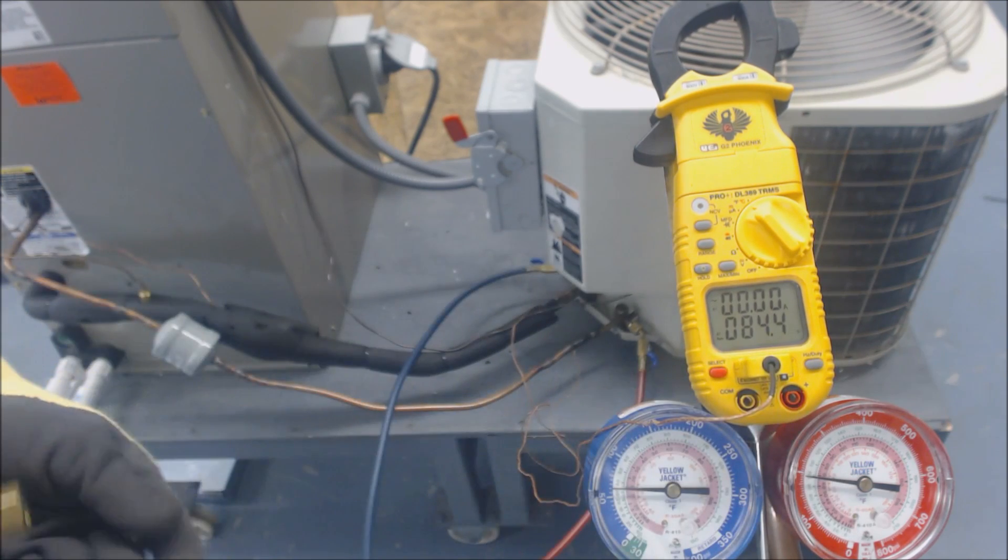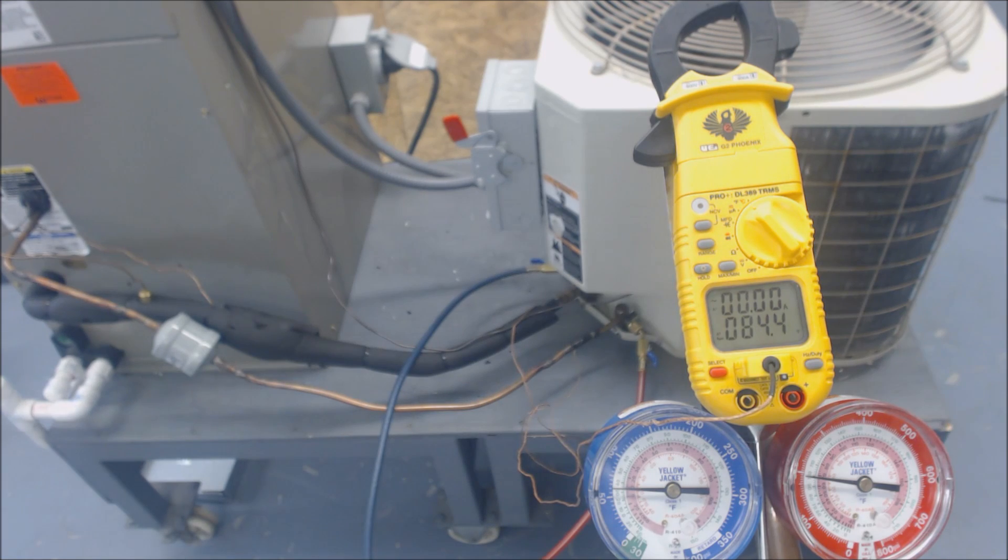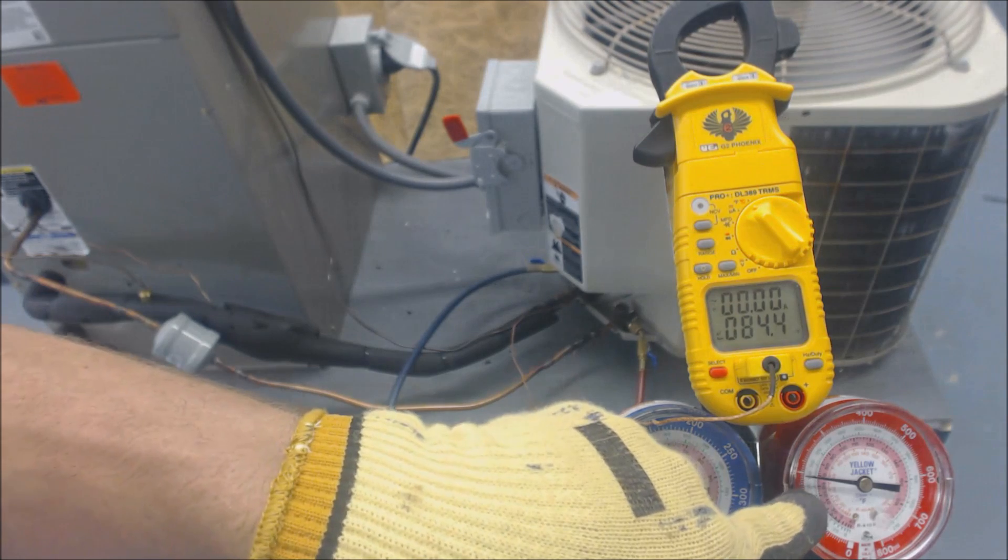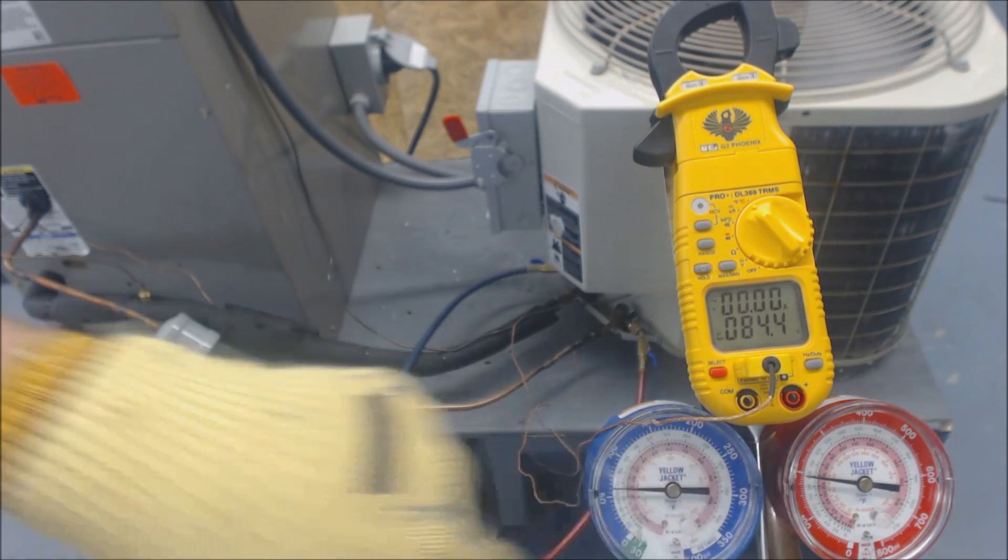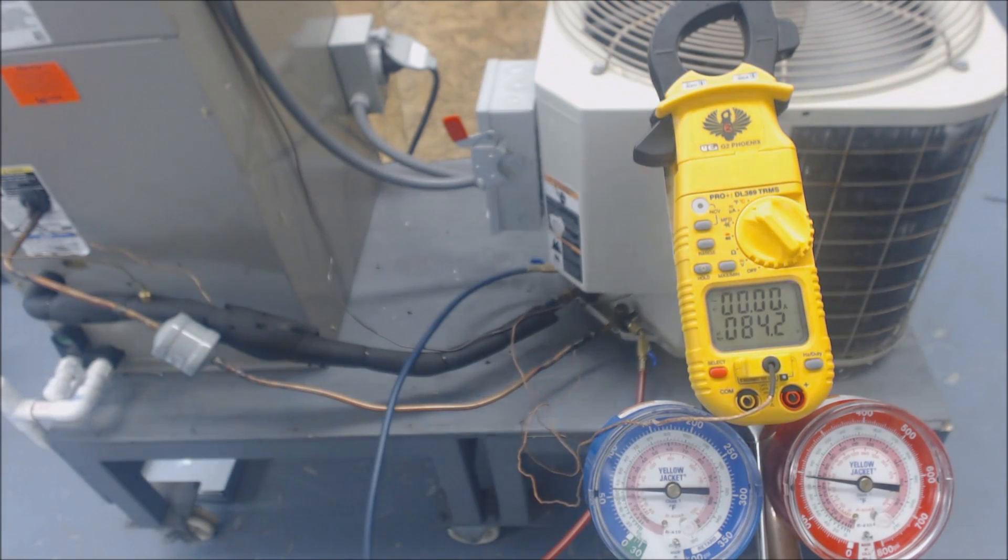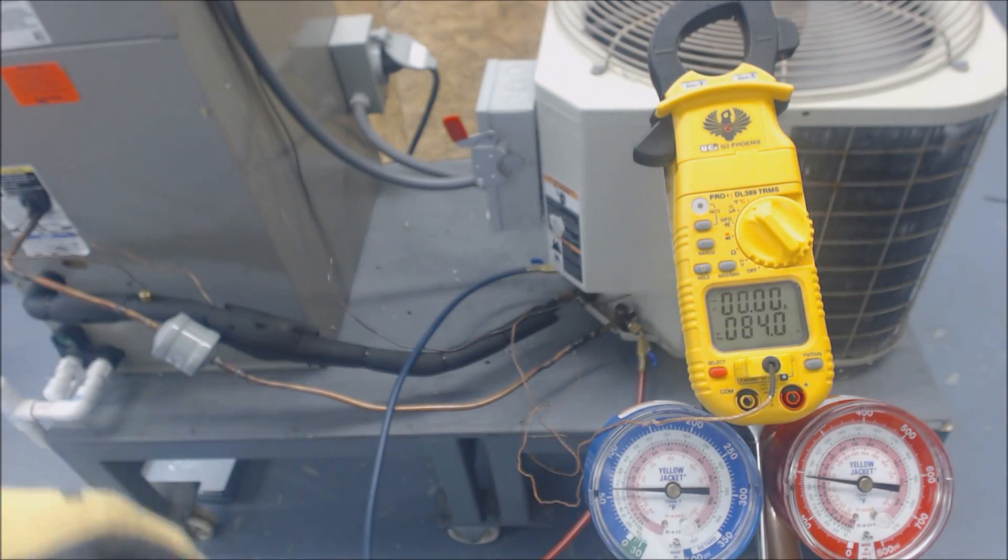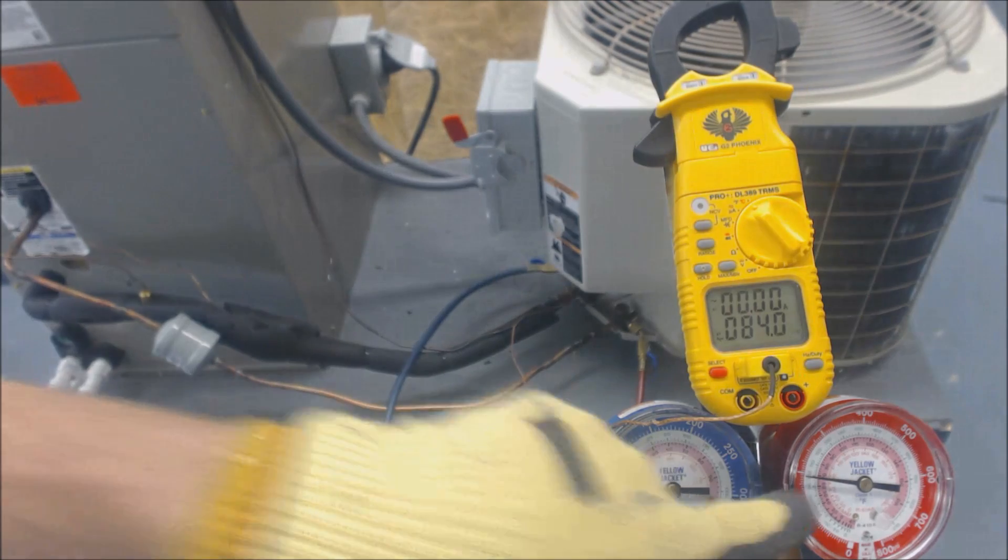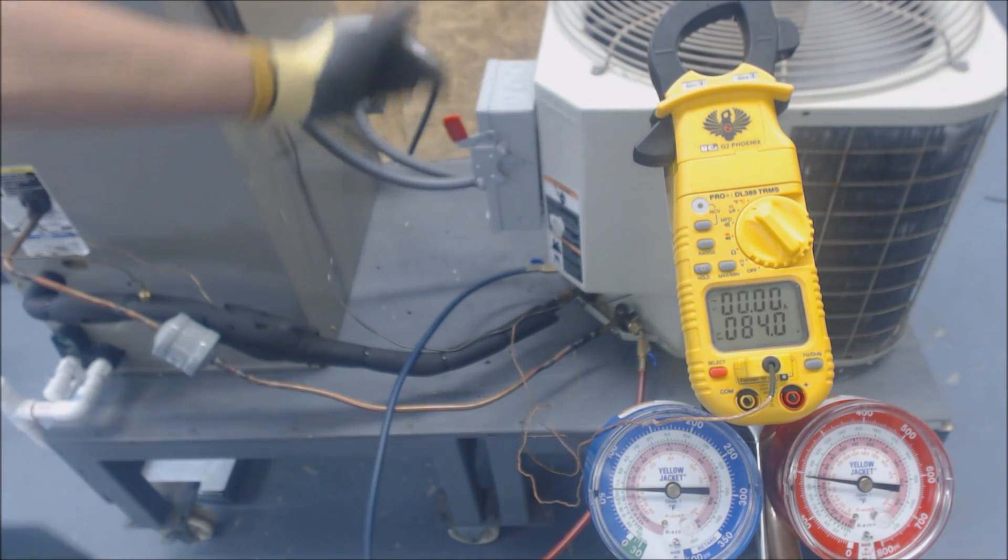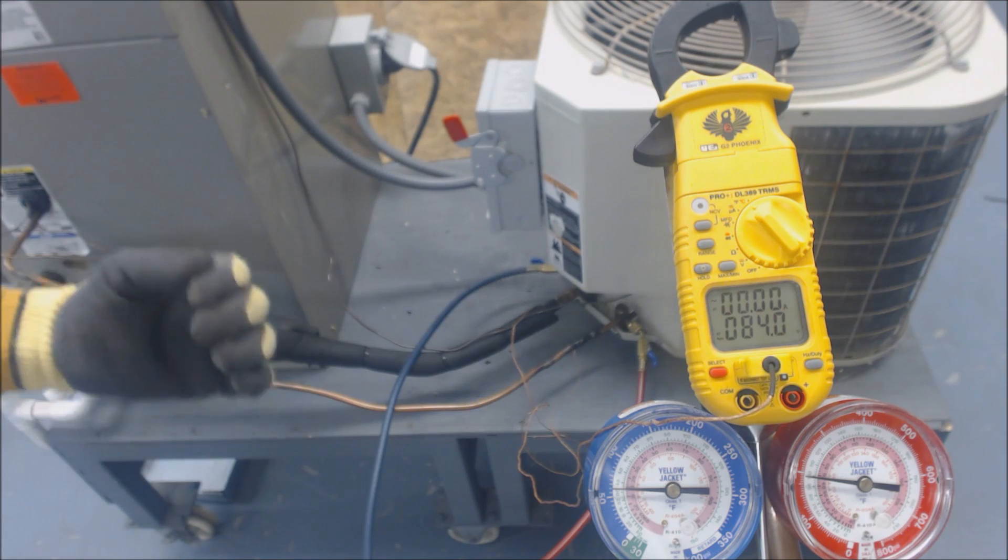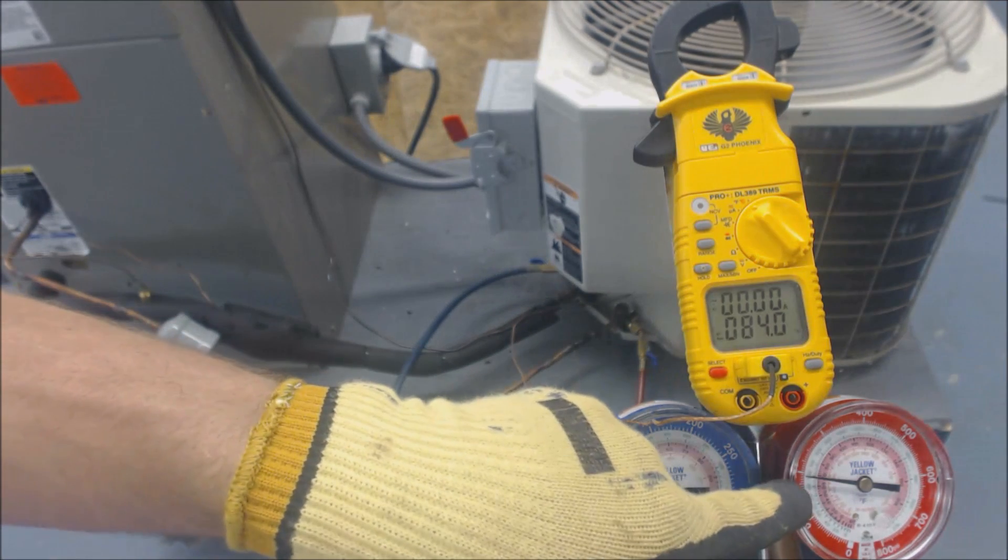We know we have a TXV, so we're going to check the charge in subcooling. We presently have about 195 PSI. If you follow that over, this unit is R22. On the rating plate it says 15 degrees of subcooling is our target subcooling.